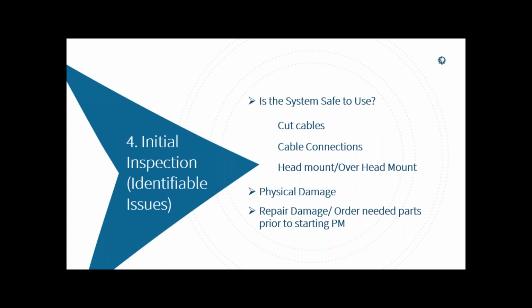Initial inspection. This piggybacks on what I said before. Is the system safe to use? You walk in there, you look at it, and it's hanging on the counterbalance assembly. No, the system's not safe to use. Check cut cables, cable connections, head mount, overhead mount. Physical damage. Repair damage, order needed parts prior to starting the PM.